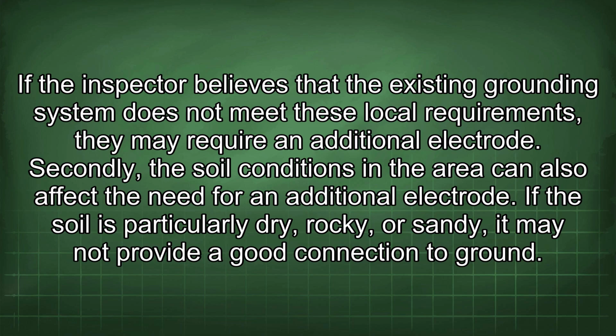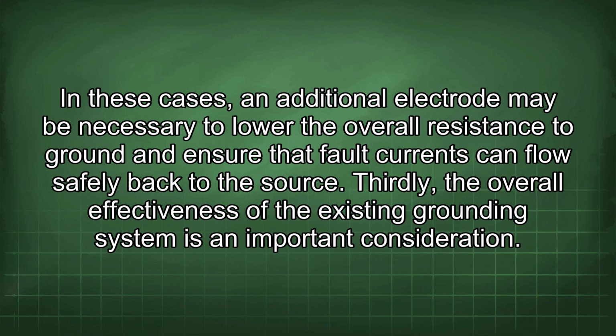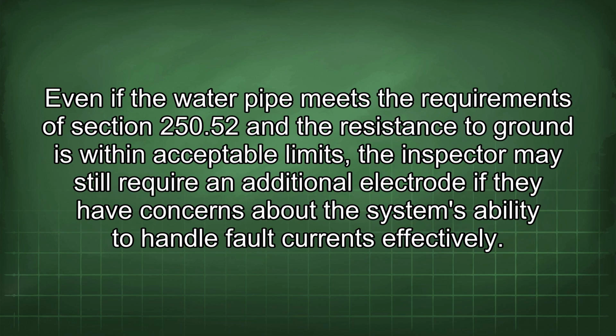Secondly, the soil conditions in the area can also affect the need for an additional electrode. If the soil is particularly dry, rocky, or sandy, it may not provide a good connection to ground. In these cases, an additional electrode may be necessary to lower the overall resistance to ground and ensure that fault currents can flow safely back to the source. Thirdly, the overall effectiveness of the existing grounding system is an important consideration.